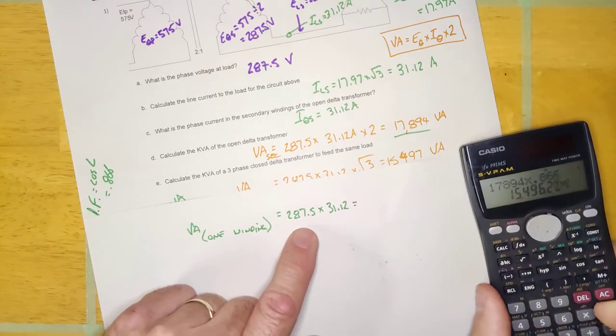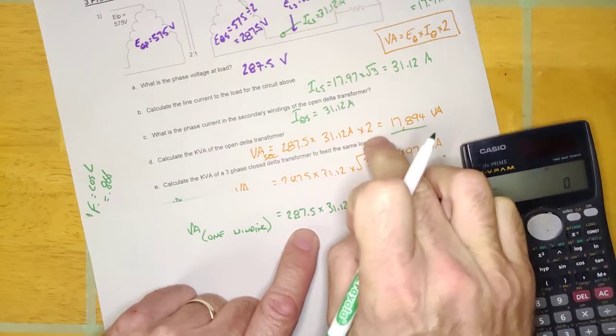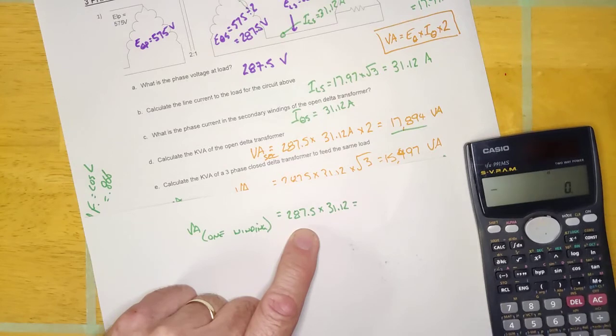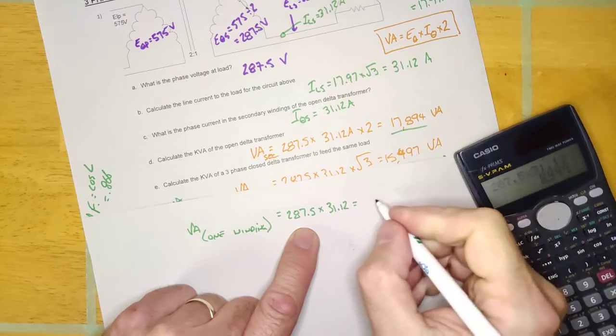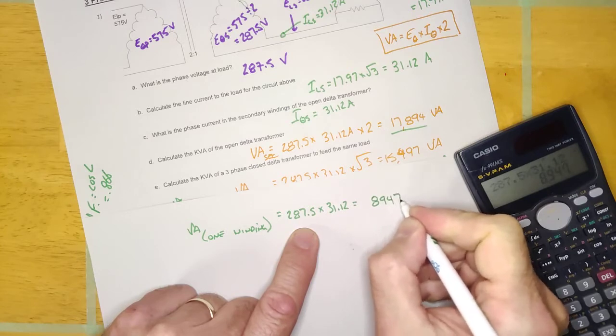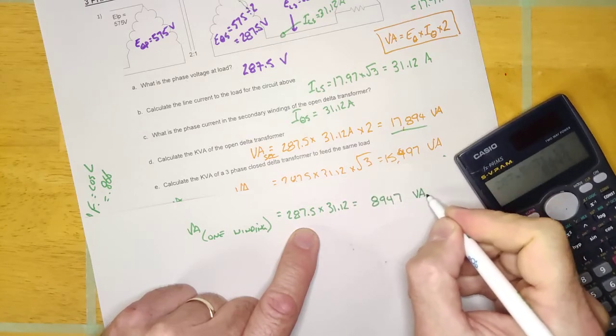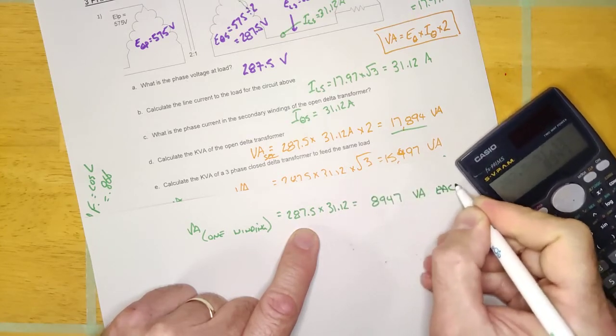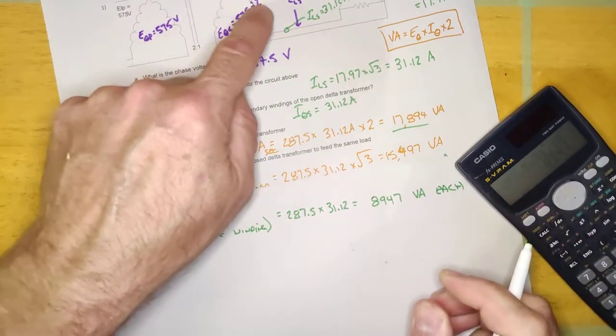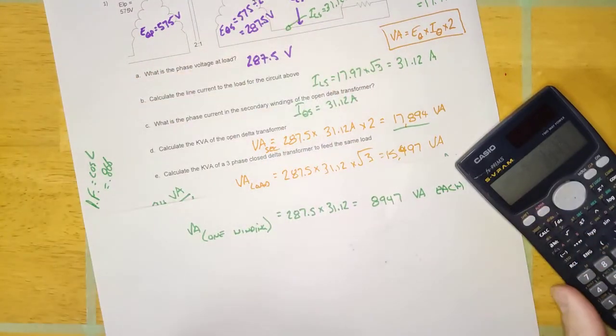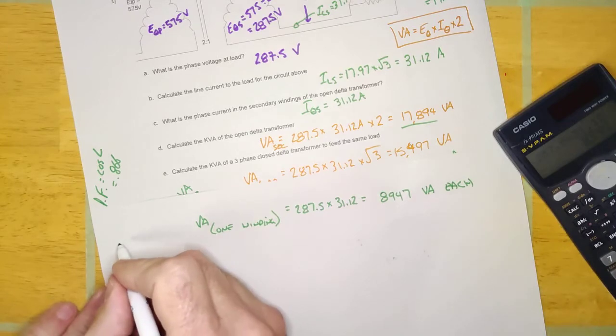So let's calculate that. Should be exactly half of 17 because we multiplied by two there. So 287.5 times 31.12 equals 8,947 VA each. The two transformers that make up the open delta transformer. So this is open delta.